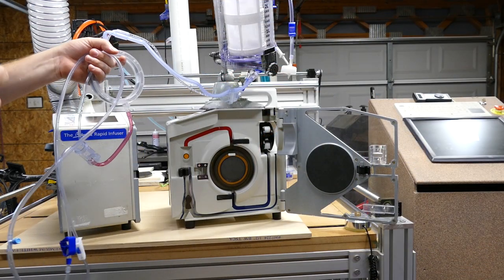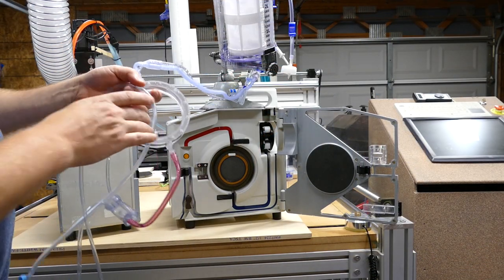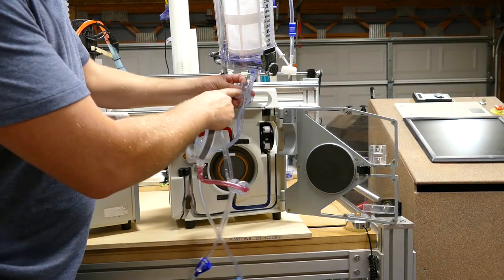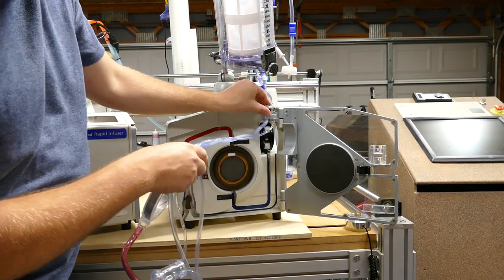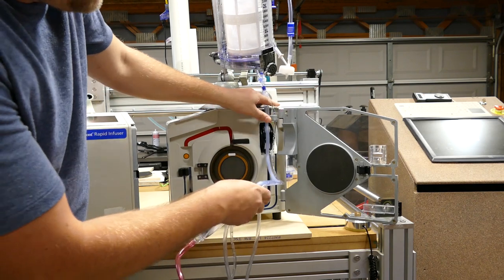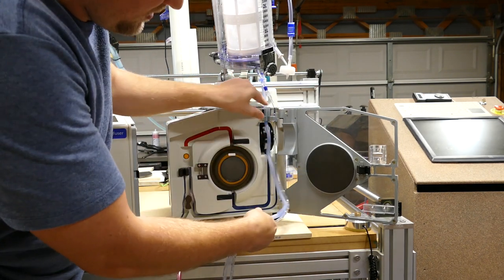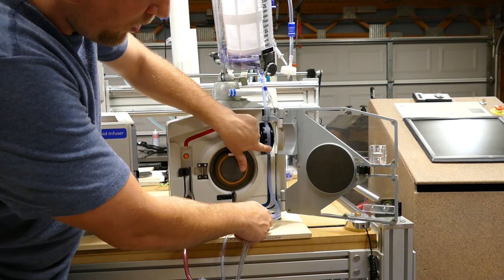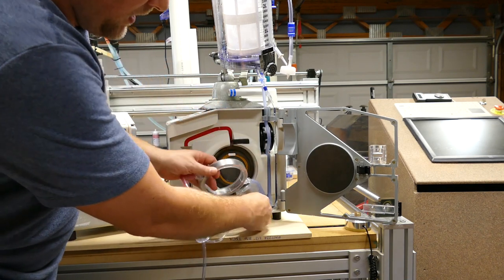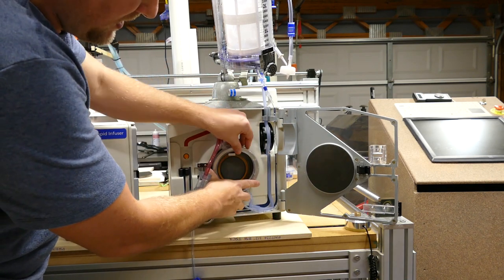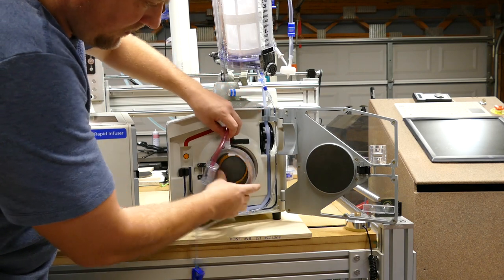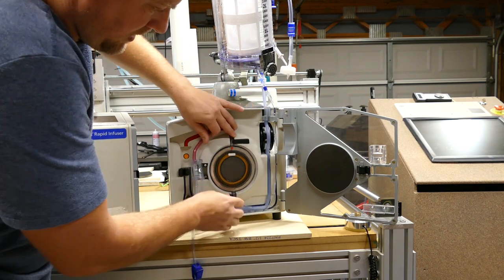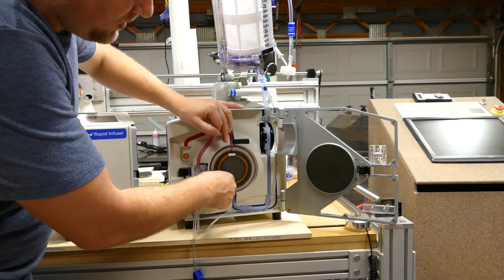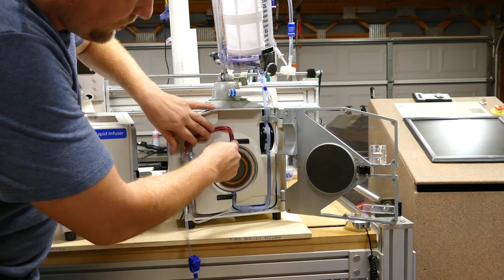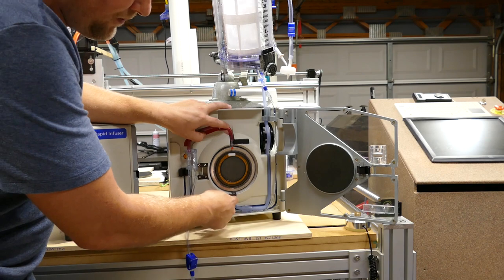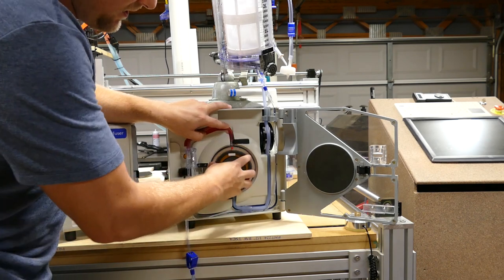Next, we're going to go ahead and we're going to load a cassette into the unit. Here, you can see the little holder for the fluid out detector. We're going to press it into its spot. The tubing is going to roll over the peristaltic pump. It's going to come down to a 90 degree angle. The inductive coil is going to press in. And you're going to route the cable up through the infrared detectors, both above and below the inductive coil.